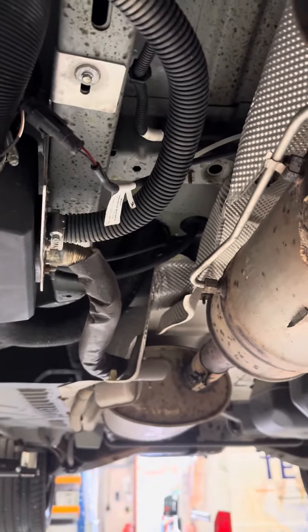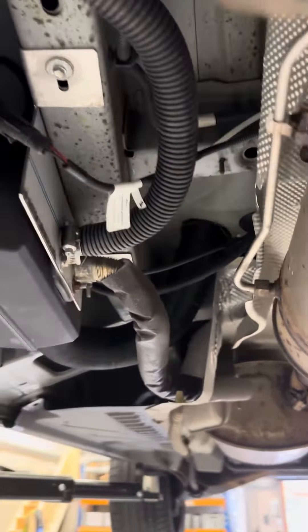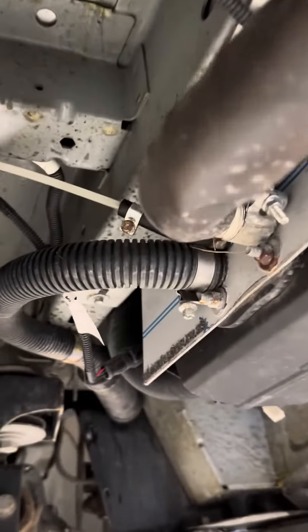There was an error code number 78 on the heater, which we've cleared down. We can probably put this down to air in the fuel line, as it's never been used by the customer. We ran the heater another two or three times and the fault code hasn't returned.